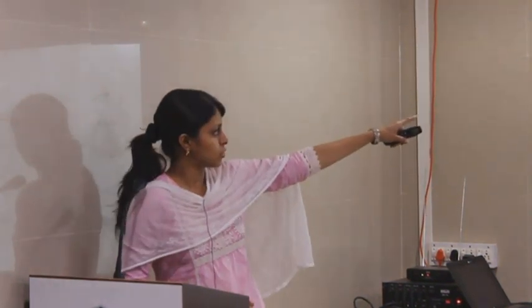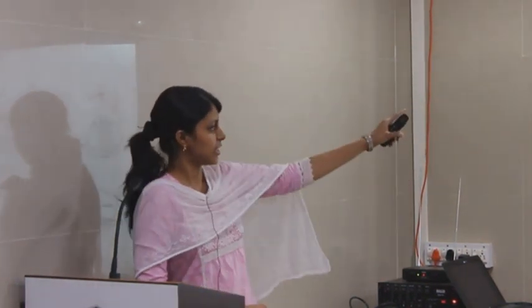The source of X-ray is the one which is black, on the opposite side of the patient, and you had one panel of detectors, and at every point it had to go and expose the patient. When this happened, your scanning time increased. With the thin pencil beam, for every section it had to go one pencil beam, shift, one pencil beam, shift. So by the time one entire section was created, it took almost 5 minutes.